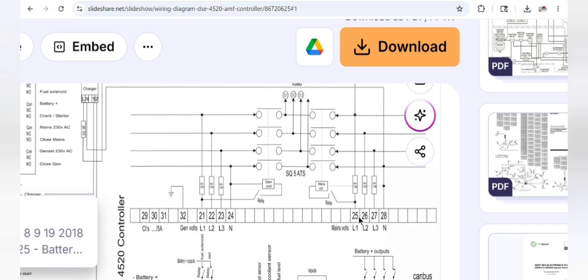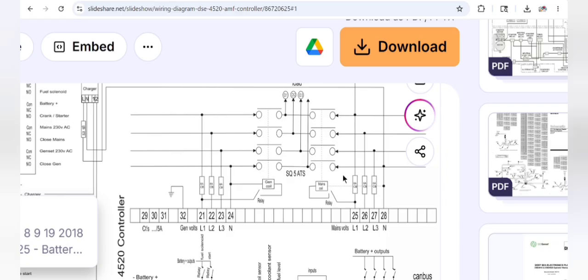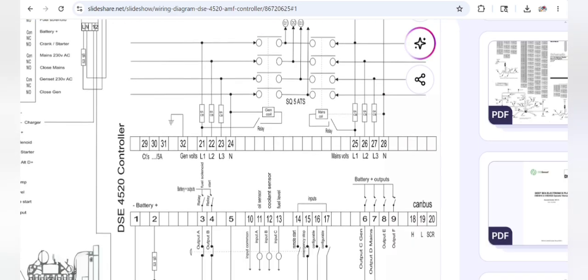As you can see here, pins 25, 26, 27, 28. Understand, this is the mains input for this controller. As you can see, pin 25 is the phase of the main controller, and it will be going to the contactor coil A1, and the ground side is going to the contactor coil.